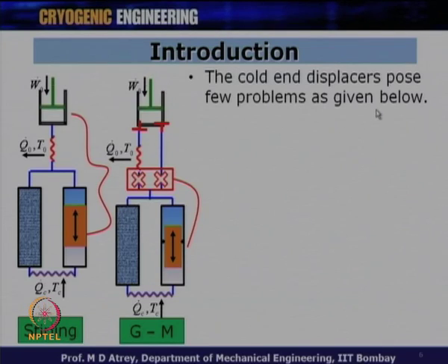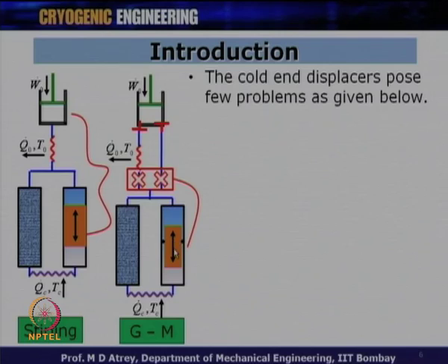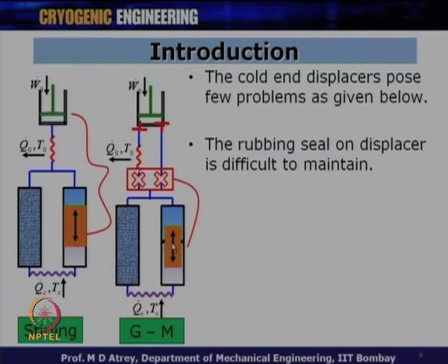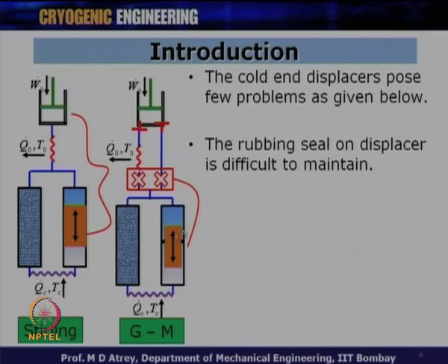The cold end displacer poses a few problems. In a GM cryocooler especially, there is a rubbing seal that works at low temperature. These seals can cause problems. The rubbing seal on the displacer is difficult to maintain and one has to take care of how it is composed. At low temperatures, there could be shrinkage, and a seal which is perfect at room temperature may not work well at low temperature.